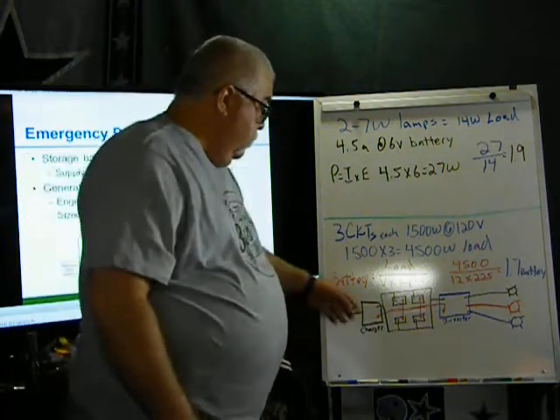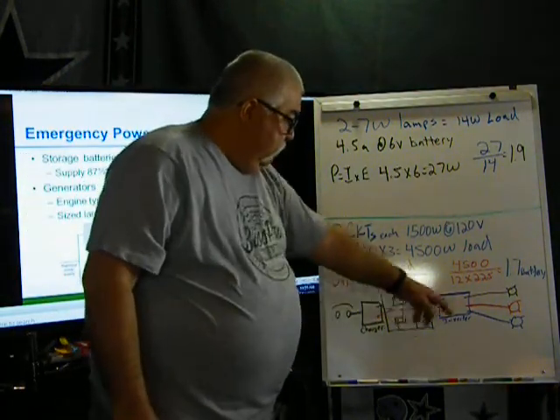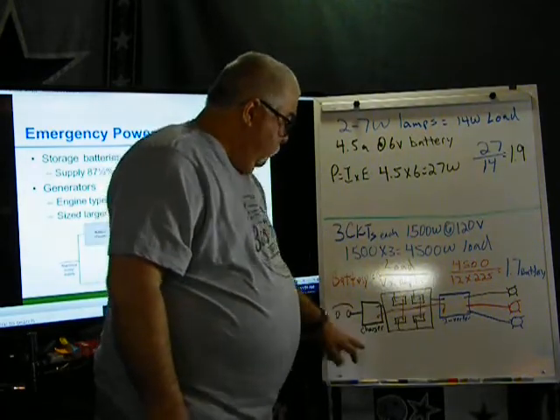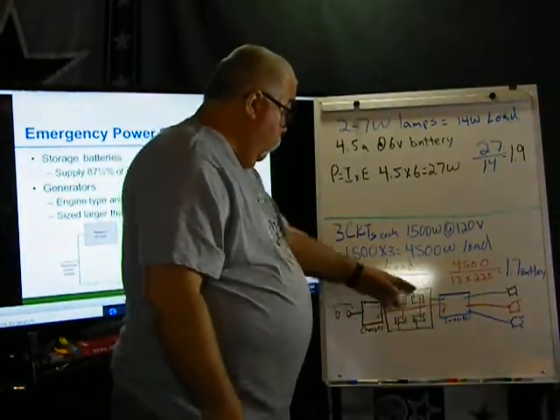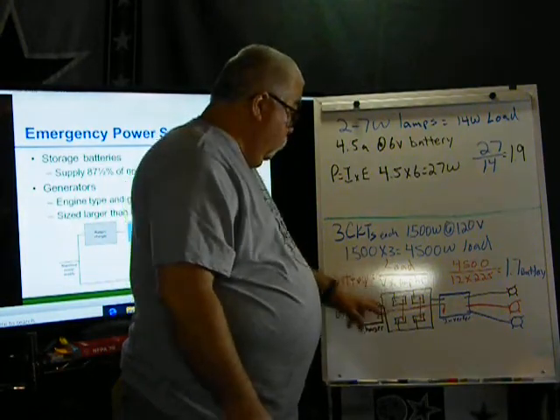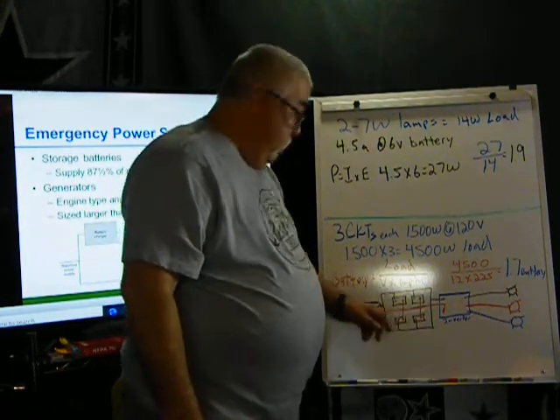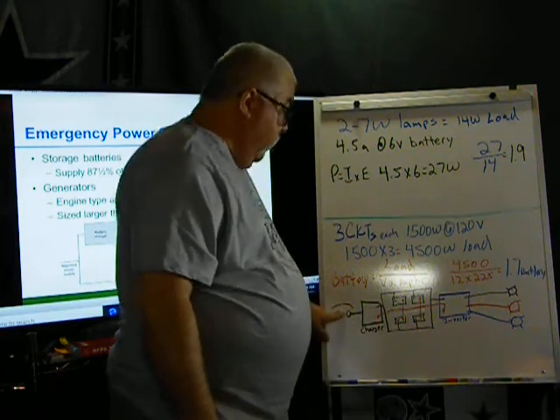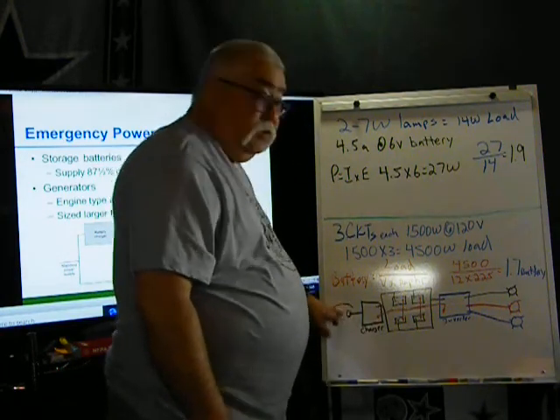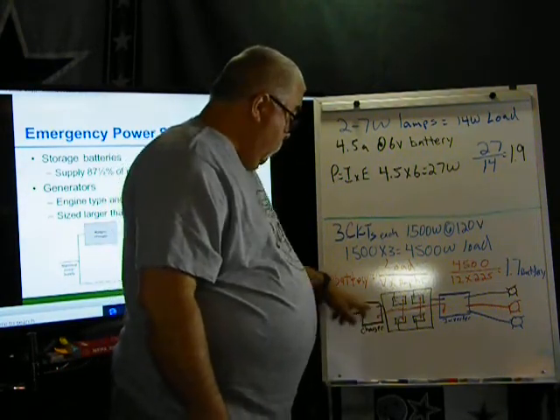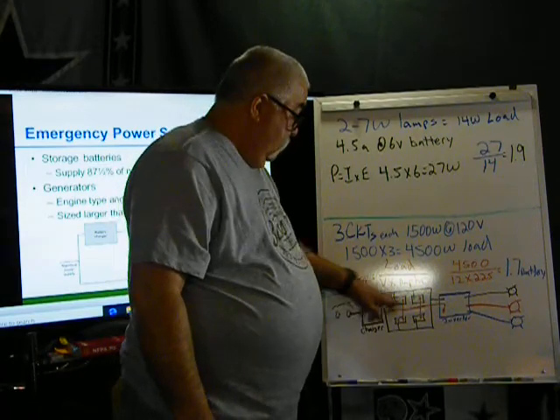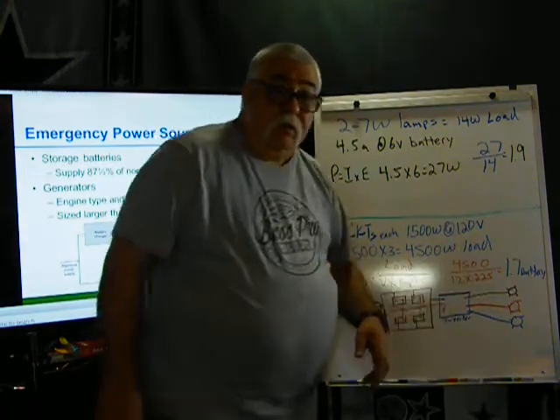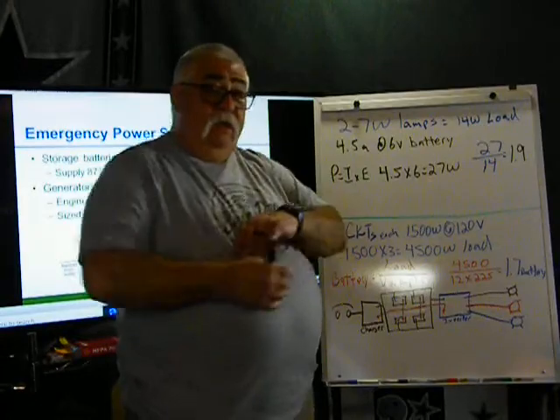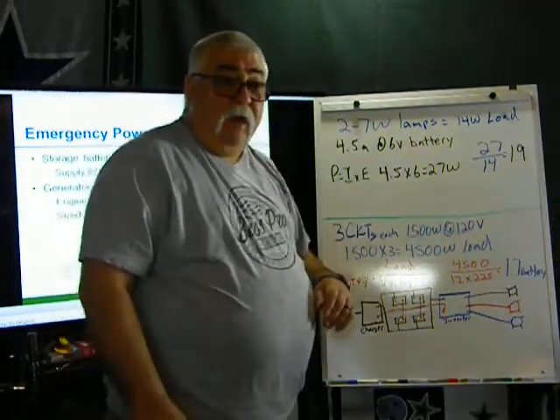Okay, so the power comes into the charger, it goes to the inverter, and I've got the power going across. I may have a little jumper coming across to feed these, or whatever it may be, or they're always fed through here. Power goes out, all the charge comes out of the battery. So I can come over here and turn this breaker off. On this one here, I can turn this breaker off. It's going to the charger. What happens? The lights all come on. So I can sit there and look at my clock, or come back in an hour and a half.